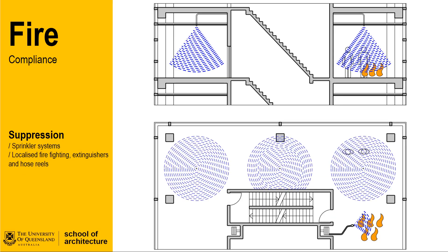Fire suppression is the third aspect of fire safety. There are three main strategies of fire suppression that are cumulative. The more basic forms are human-operated suppression that includes fire extinguishers and fire hose reels, intended to eliminate small fire risks as soon as they occur, and also to help combat a fire threat that may be blocking the pathway to an exit. Firefighters may also use fire hose reels to assist their suppression of a fire. Sprinkler-based suppression systems are operated automatically to douse larger fires. They tend to be installed in high-occupancy buildings or high-volume buildings with a large number of fire source features, such as warehouses and other goods storage areas.